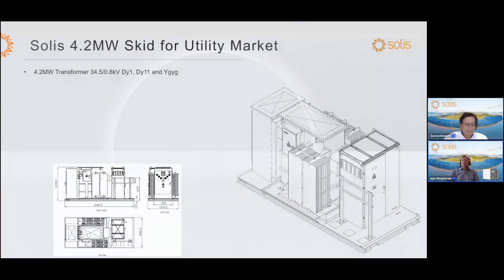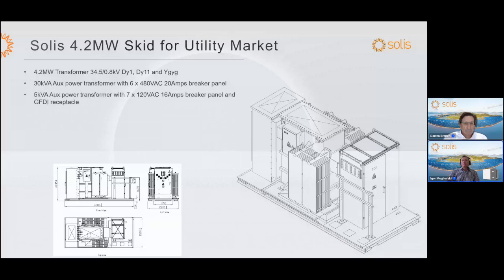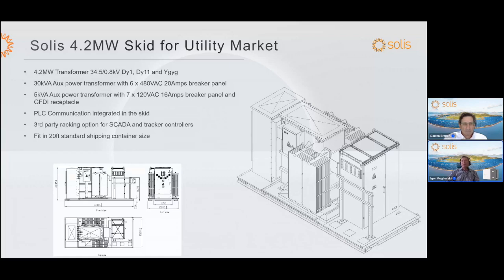So it could be connected to different utilities or interconnections. 30 kVA auxiliary transformer, 6 480 volt breakers with 20 amp ratings, and then a standard 5 kVA transformer with 7 120 volt 16 amp breakers and GFDI receptacle. PLC communication is integrated in the skid, so you don't need another enclosure. All the communication devices could be installed in that enclosure. Third-party SCADA located on the side externally could also be wired and connected in the skid. One skid fits in a 20-foot container, and 2 skids could fit in a 40-foot container, so you can save some costs by shipping 2 skids per container.